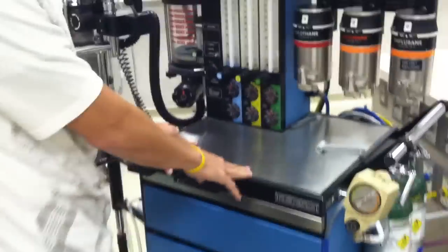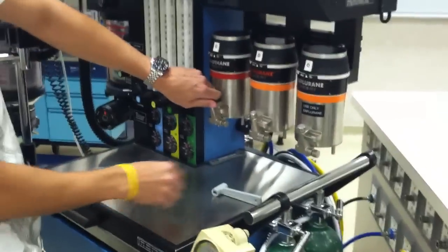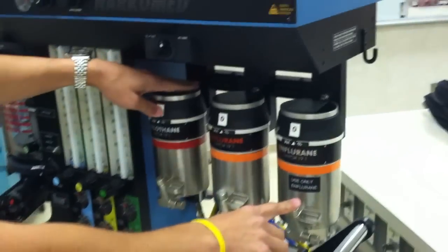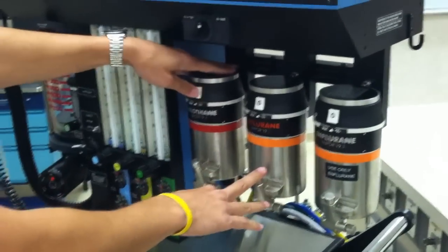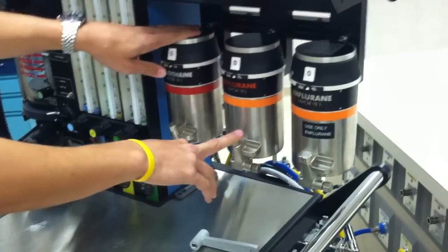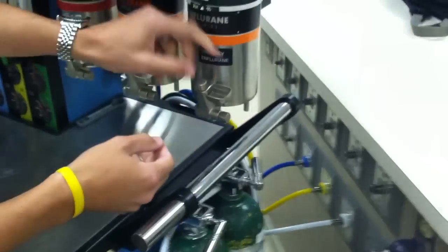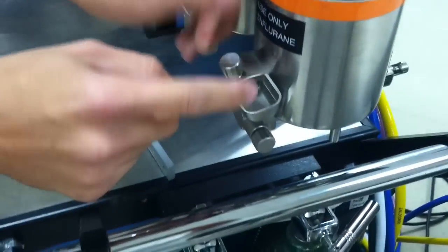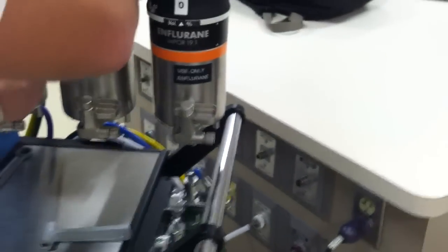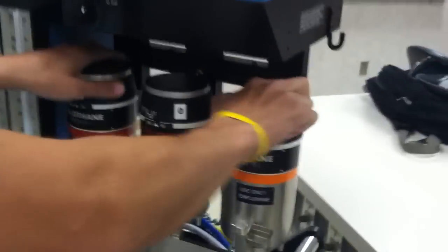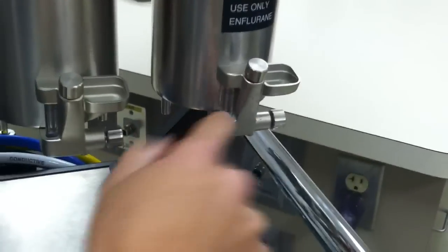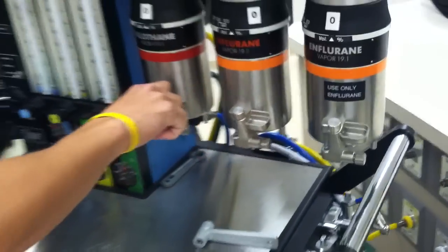So this machine doesn't have a low pressure system check, but we still want to make sure that we fill up our vaporizers and that we check the interlock system. If you ever come across these old ones, you twist this knob, there's a little seal, pour it in here and close it, and then you just check the interlock system. And then it fills up here. So we just want to make sure we're in line. So that's how you do it. Make sure these are all tight.